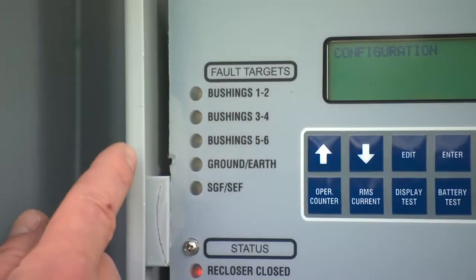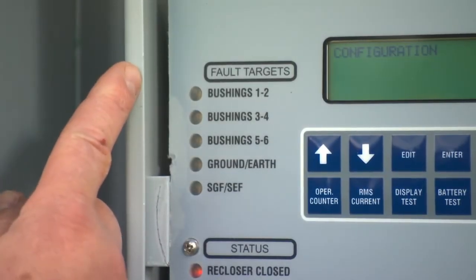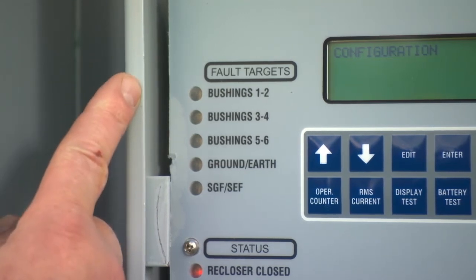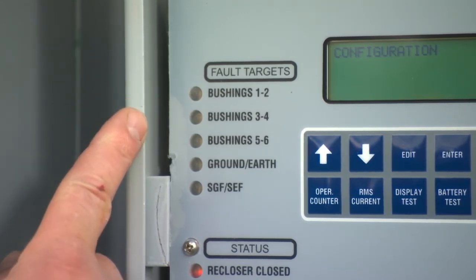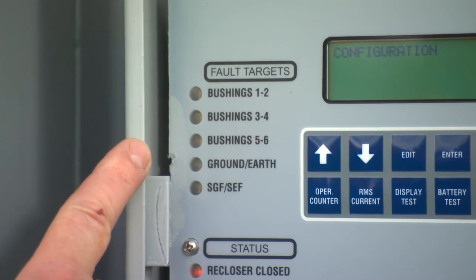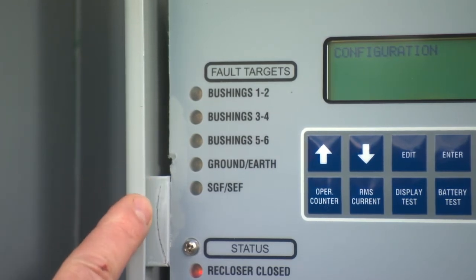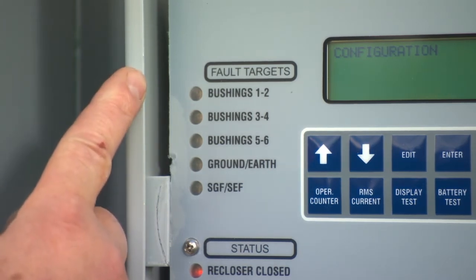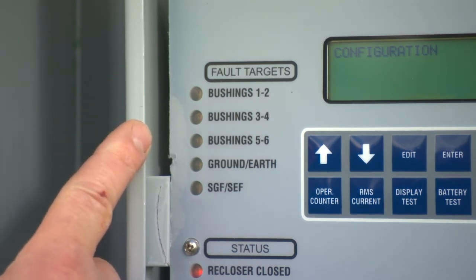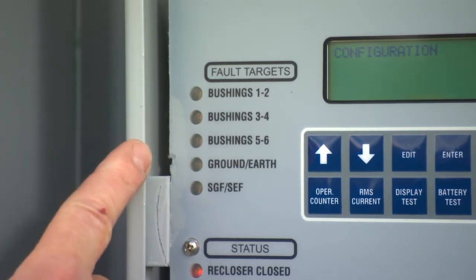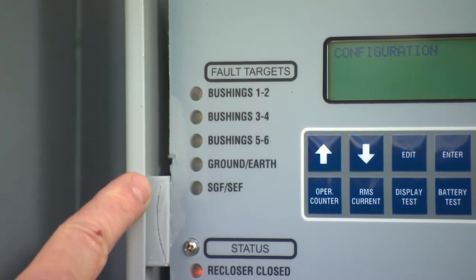A closer look at the left-hand side of the control cabinet, you will see the fault target indicators. These are labeled as bushings 1 to 2, 3 to 4, 5 to 6, ground, and sensitive earth or SGF-SEF. The latter will not display as that feature is turned off. All other indicators will activate whenever a fault occurs on your A, B, C, or red, white, and blue phases. Ground will also activate whenever an earth fault occurs.